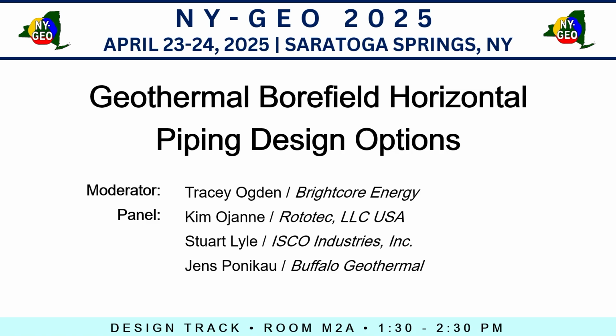But again, I don't have a problem with reverse return headers. But for me, it's a cost and effort practice where I'd rather be done quicker and do another job than have this, for me, more complex header design in there. But I do avoid balance valves wherever I can. I mean, I've never put them anywhere on the source side.